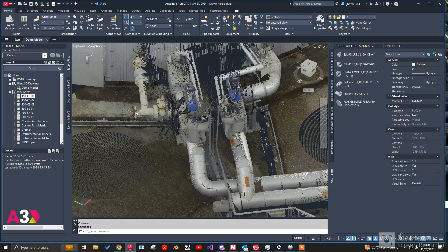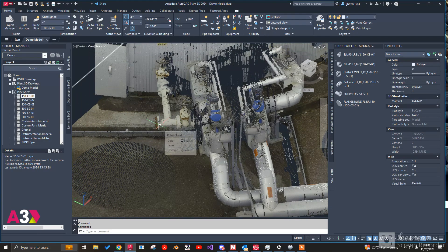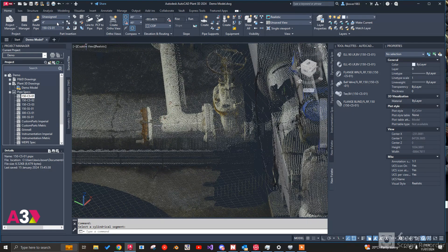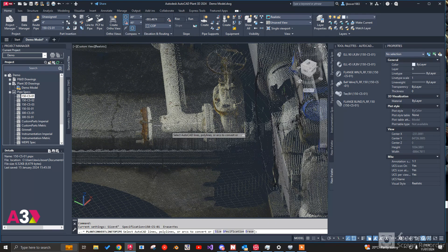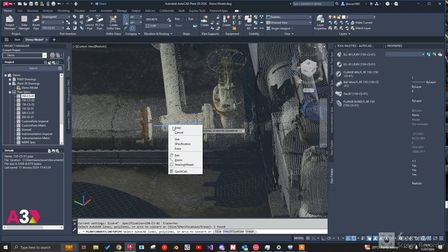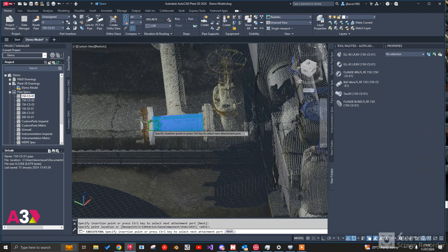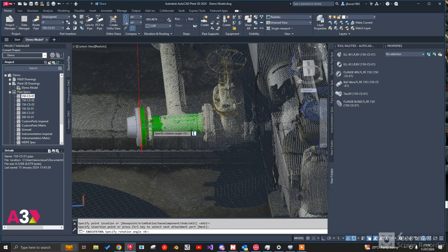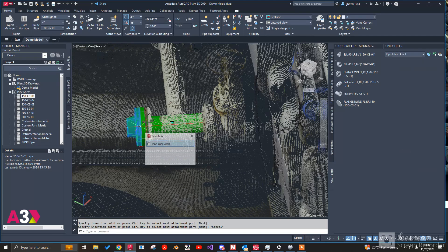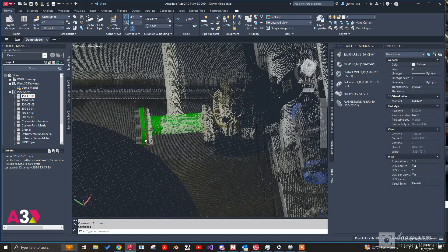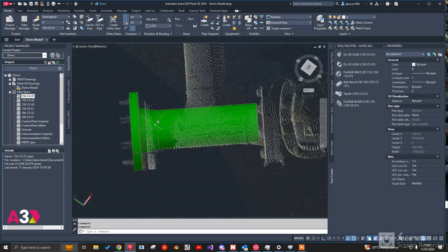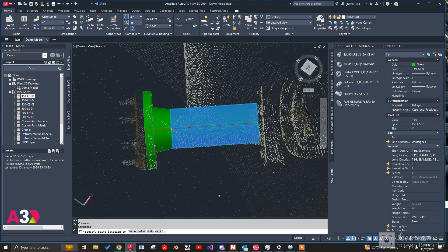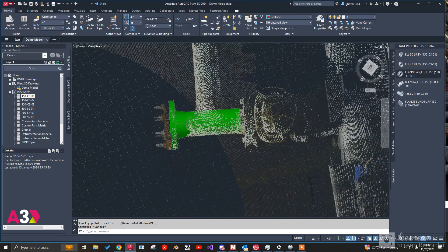So I'm going to tie into this existing line over here. I know it's 4 inch. I'm going to extract a center line from the point cloud data. And it's highlighted pink there because it's picked up on the pipework and I've set it to 150 pound carbon steel spec. And I'm just going to add that line in like so. Then we're taking the weld neck flange. So what I'm doing here is just modeling what was already there basically. I'm just going to drag this back like so. Turn the properties off and speed things up a little bit.